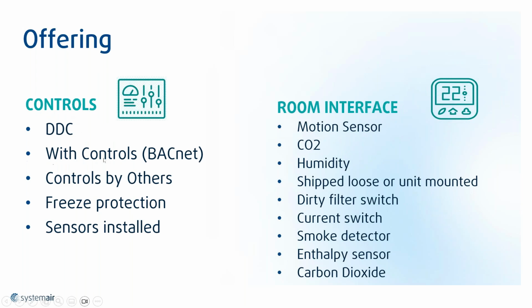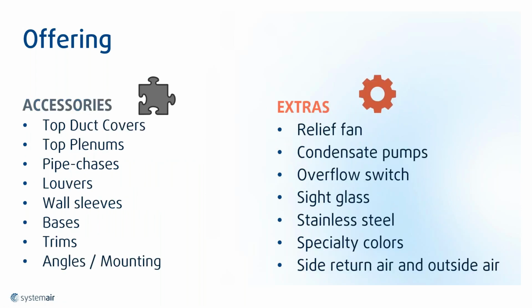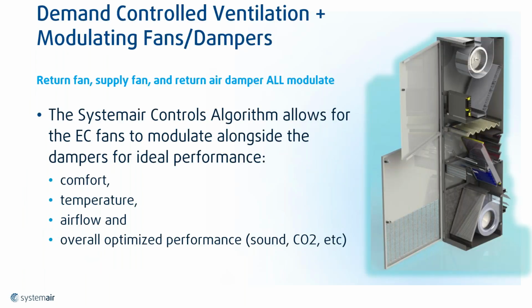Controls, your options: you have DDC, you can just get the terminal strip, or you have a BACnet controller that's tailor-made or suited for our units. So it modulates dampers, the fans, etc., in tandem with the CO2 levels of the classroom and the inside and outside temperatures. We overpressurize the room by about 10 to 20 CFM. So room interface, motion sensors, CO2, humidity, you can get a mix of these sensors or integrate it all into one, or mount it on our cabinet, or mount it on the wall of the classroom, shipped loose. As I mentioned before, everything you see here in this offering is available and selectable in our selection software. So if you do hydronic piping or hot water, chilled water, combo coil, you have your option to choose any piping you want. So you could have Y strainers, control valves integrated into the cabinet, and we do that with our piping department in-house.